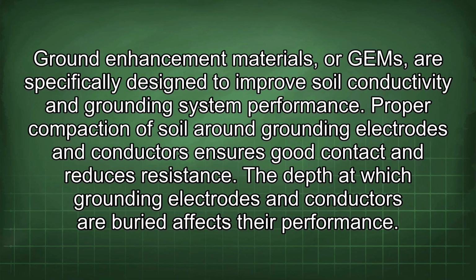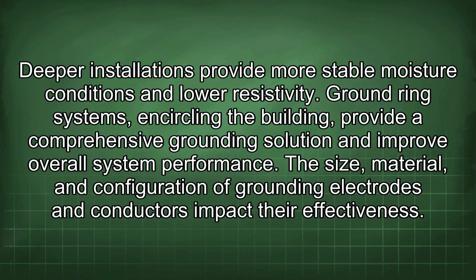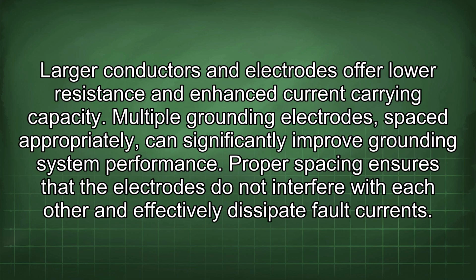The depth at which grounding electrodes and conductors are buried affects their performance. Deeper installations provide more stable moisture conditions and lower resistivity. Ground ring systems, encircling the building, provide a comprehensive grounding solution and improve overall system performance. The size, material, and configuration of grounding electrodes and conductors impact their effectiveness. Larger conductors and electrodes offer lower resistance and enhance current carrying capacity.